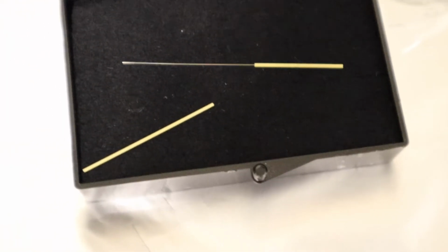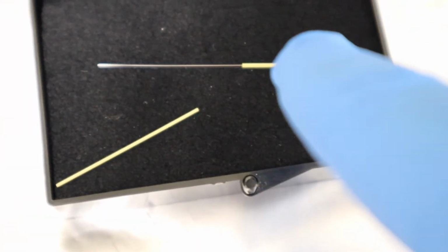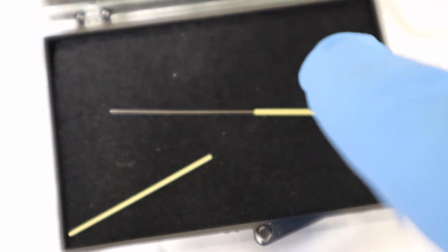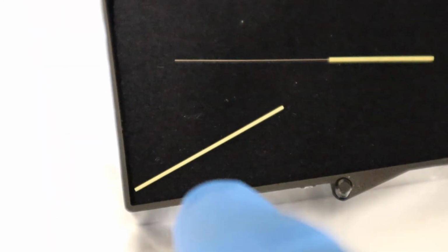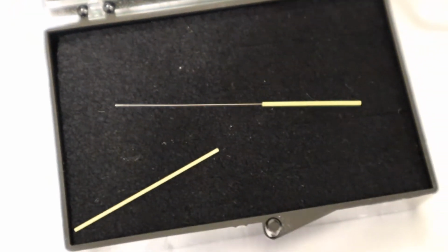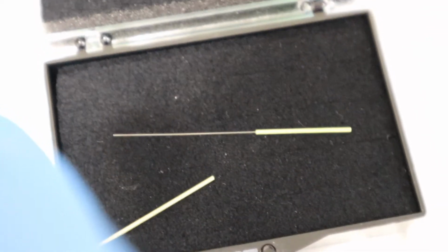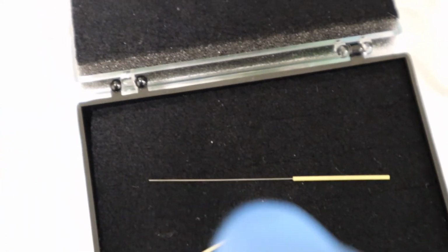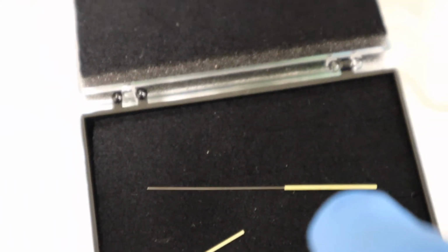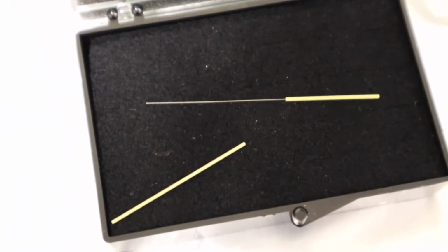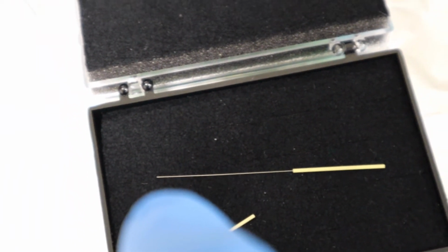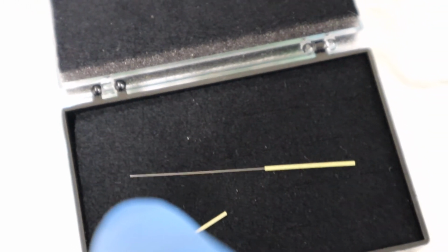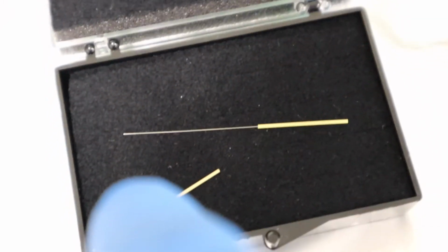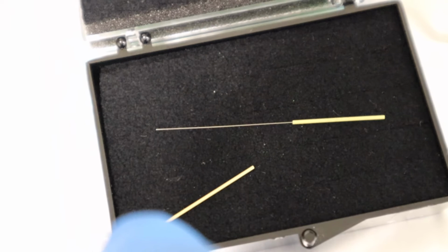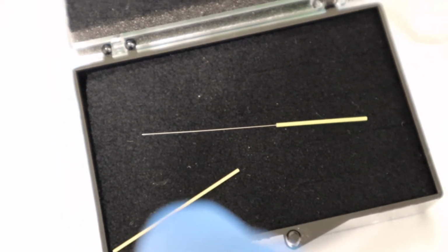So on the right you'll see the emitter with the protective yellow sleeve on it, and I'm going to take that one off, and I'm going to put this one on. Now I'm going to slide this one on from the blunt end so that I don't damage the sharp tip that's underneath the protective sleeve. And then I'm going to slide it on just so that there's a little tiny bit of the stainless steel emitter on the blunt end, protruding just beyond the sleeve, and then I can insert it into the electrospray T.